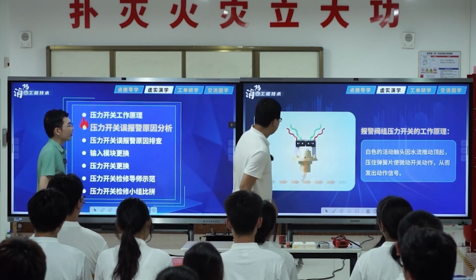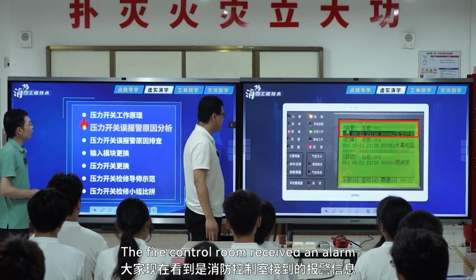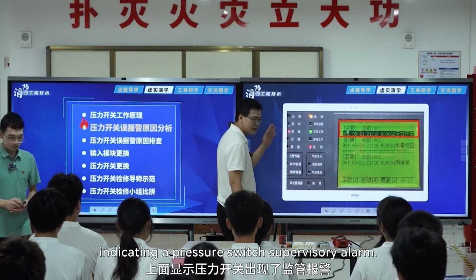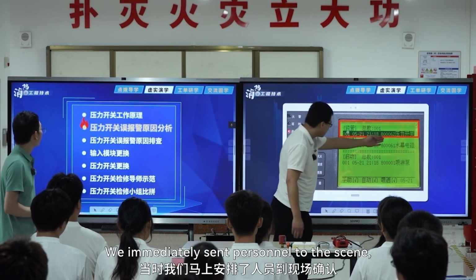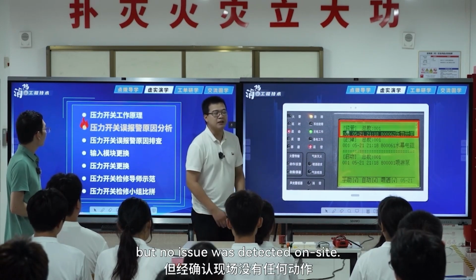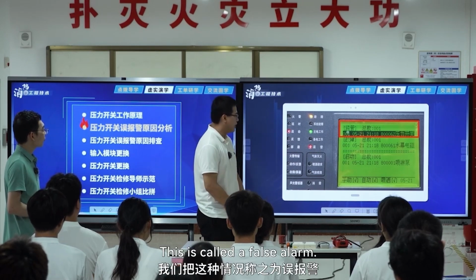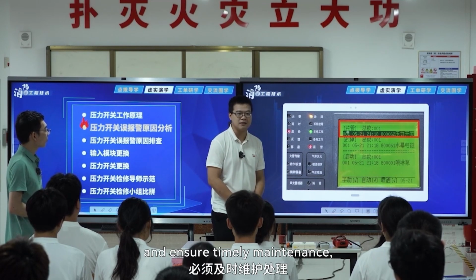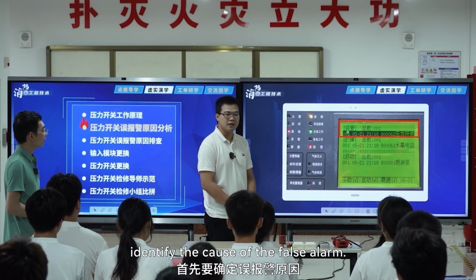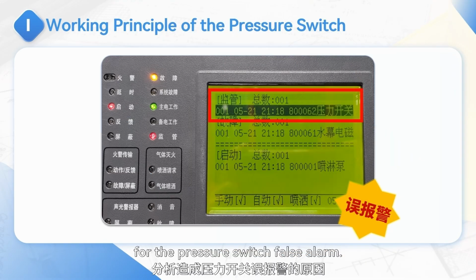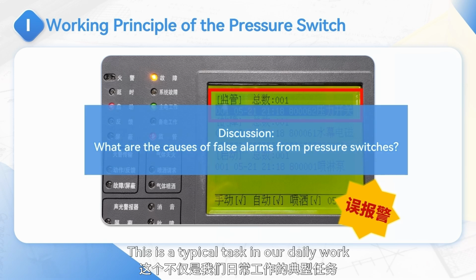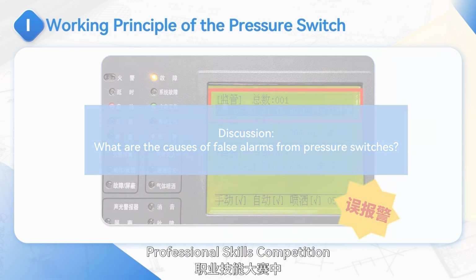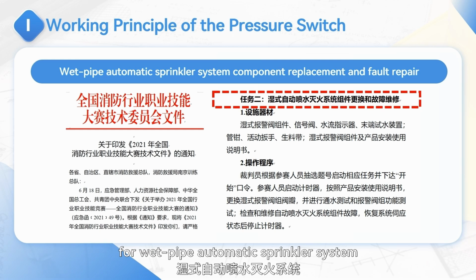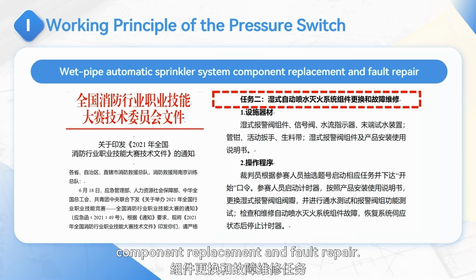Hello, everyone. The fire control room received an alarm indicating a pressure switch supervisory alarm. We immediately sent personnel to the scene, but no issue was detected on site. This is called a false alarm. To avoid wasting resources and ensure timely maintenance, we must quickly identify the cause of the false alarm. Your task is to analyze the reasons for the pressure switch false alarm. This is a typical task in our daily work, and is also part of the National Fire and Rescue Professional Skills Competition for Wet Pipe Automatic Sprinkler System Component Replacement and Fault Repair.